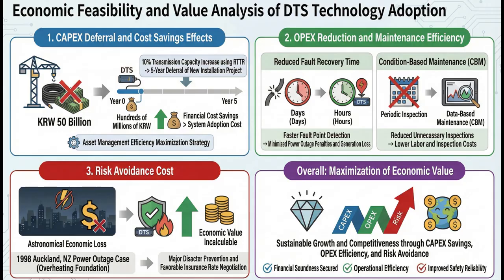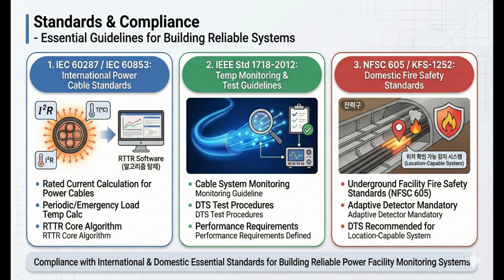The business case can be explained in 3 parts. First, by improving utilization through RTTR expansion, investment can be delayed, deferring CAPEX. Second, it reduces outage time by quickly identifying fault locations and cuts unnecessary inspections, lowering OPEX. Third, the largest value is avoiding the risk cost of major incidents, such as fires and blackouts. Ultimately, DTS should be viewed not as an expense, but as an investment that improves safety and operational efficiency at the same time. For reliable implementation, standards-based design is essential.